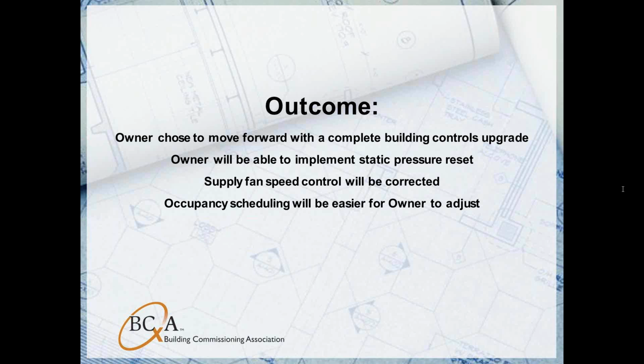Okay, thank you. And Mark, I'll chime in for a second too. As Mark pulled this together, there's a couple of things I wanted the audience to take away. This started as a utility retro commissioning project, kind of naively, let's get in the building and see some things. Some of the things that jumped out, right? So we said before, more pumps running than you anticipated, random things shutting down. These are all the problems that we sifted through and drew out of conversations with the operations staff: differential pressure not being met, low delta T, economizer set points and lockouts for economizer mechanical cooling, fans running at 100%. Those are all things that, as you go through the screenshots of the building, looking at the BAS, are things to look for.